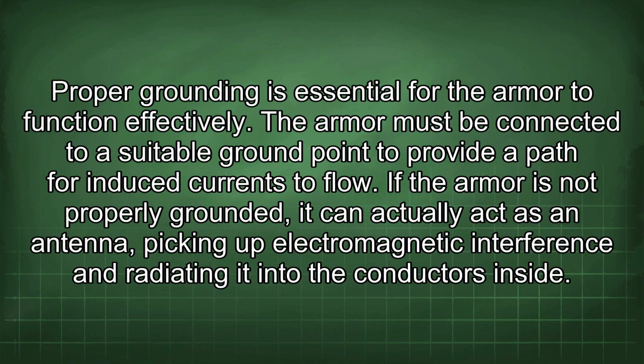Proper grounding is essential for the armor to function effectively. The armor must be connected to a suitable ground point to provide a path for induced currents to flow. If the armor is not properly grounded, it can actually act as an antenna, picking up electromagnetic interference and radiating it into the conductors inside.